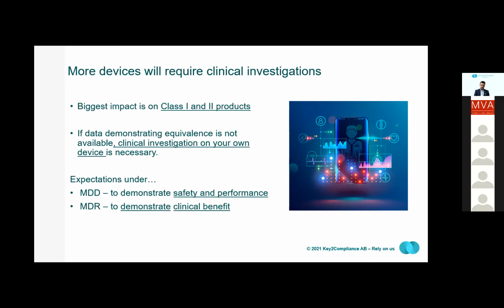Under MDR, equivalence will be much harder to demonstrate. Devices need to be equivalent with respect to technical, biological, and clinical properties. And the manufacturer needs to demonstrate access to the equivalent device technical data. Also, under MDR, device studies should demonstrate clinical benefit. And this requires the clinical investigations to be designed with additional and, in a lot of cases, complex endpoints, more intricate study setups, and potentially larger sample sizes. Next slide, please.